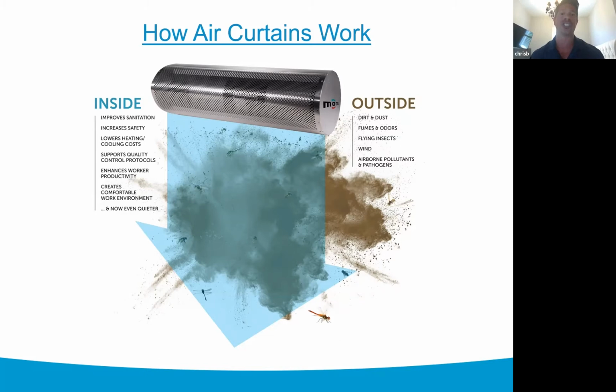So what the air curtain is going to do is raise up that conditioned inside air. We're going to raise the velocity of that air through a series of motors, depending on the lengths. We call them motor fan assemblies, either a cross flow design or a forward curve centrifugal design, okay? So that's the operation. And what we're doing is we're using air as an insulator.